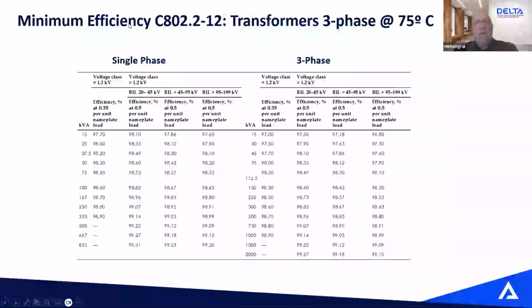In that minimum efficiency standard, sorry, here it says 12, but it's 18. So in that standard for transformers, we have tables to follow. Depending on your kVA and voltage class, we have different efficiencies to meet. Again, low voltage, so anything below 1.2 kV, at 35% load. Anything with a BIL of 20 and above is at 50% load. So the more you go up in kVA, the more you go up in voltage class, the more efficient it must be. And you have tables for single phase and three phase.